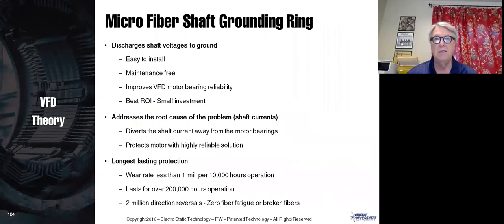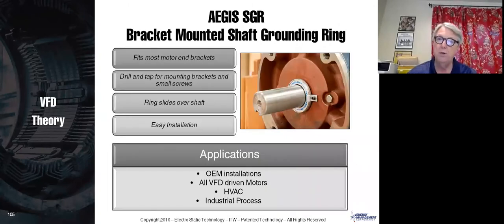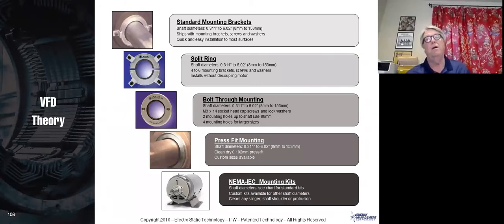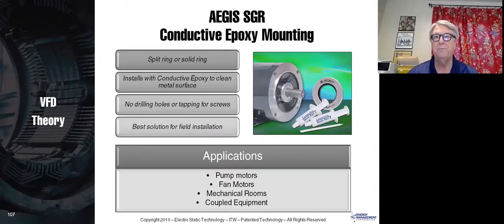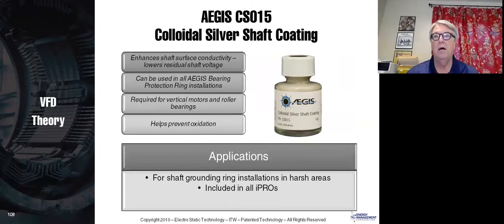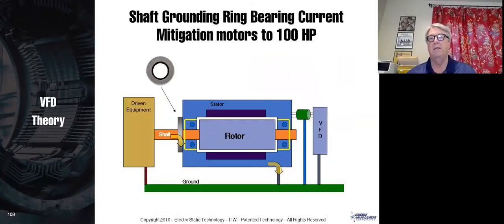In this case, and let me show you a picture. You have a shaft grounding ring here, and it literally shorts the shaft to the frame. So we're basically shorting that shaft to the frame and thus limiting any voltages from building up. The big advantage of shaft grounding is it's a lot less expensive than ceramic bearing. There are different ways to mount it. Recommendation is, and let me do this, then I'll come back to that slide.